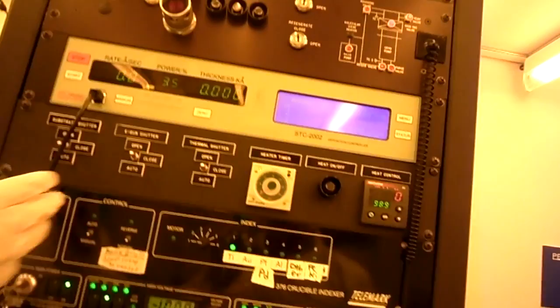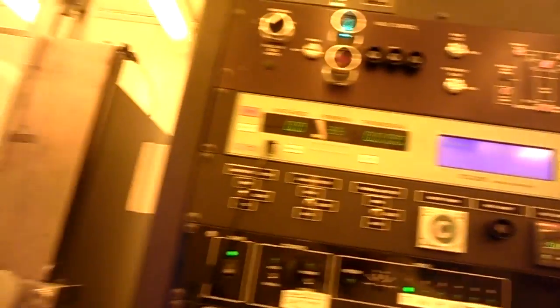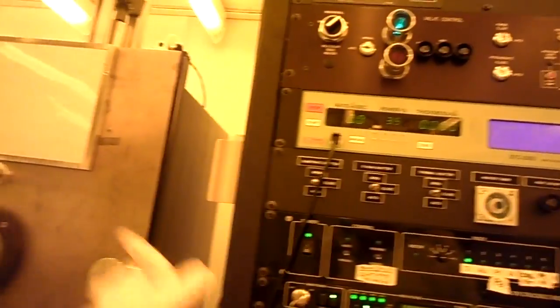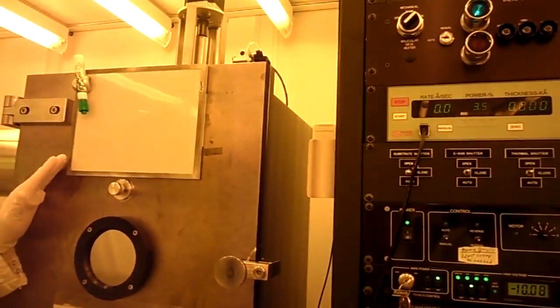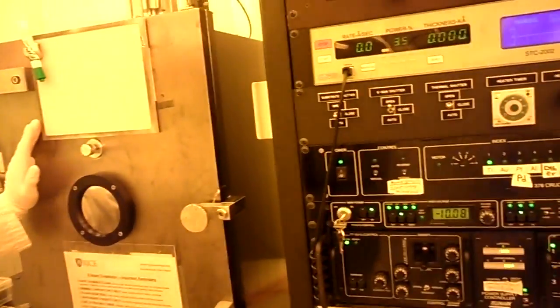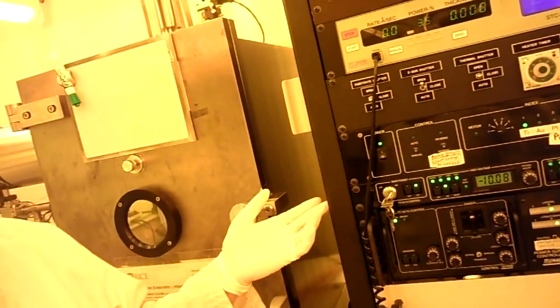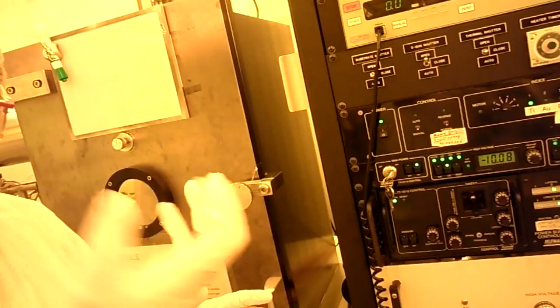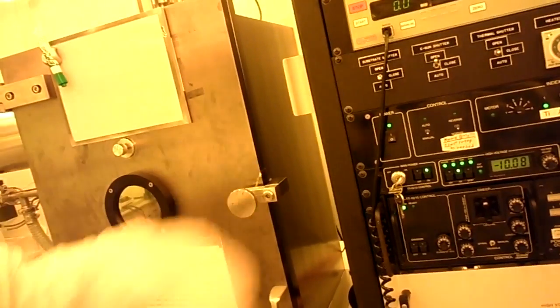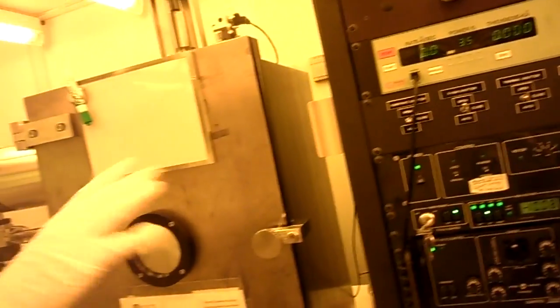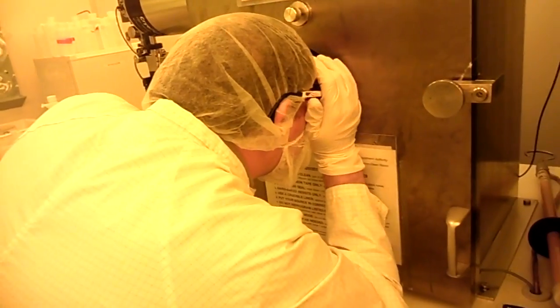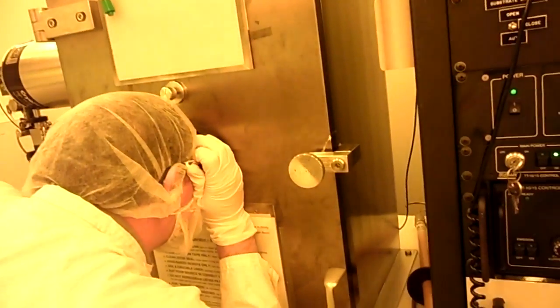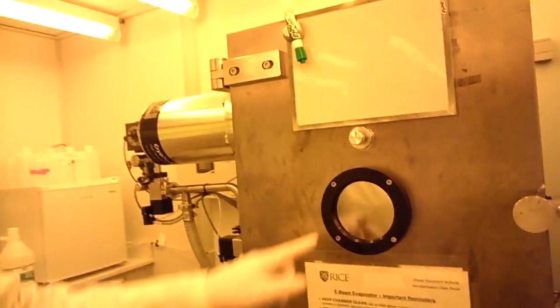Now, we've got both shutters closed. The detector is over here, right? If I don't open this shutter, I'll never see the rate that I'm getting. So I need to open this now. And if you hear noise, that's just compressed air that actuates the motor for these shutters. They're all compressed air actuators. One of them has a little bit of a leak to it. It's okay. It's just compressed air. It's not a big deal.